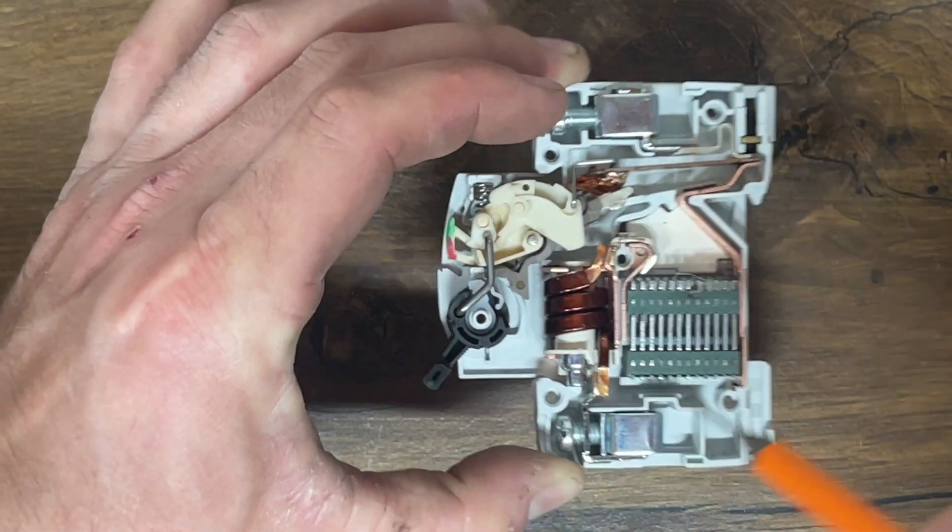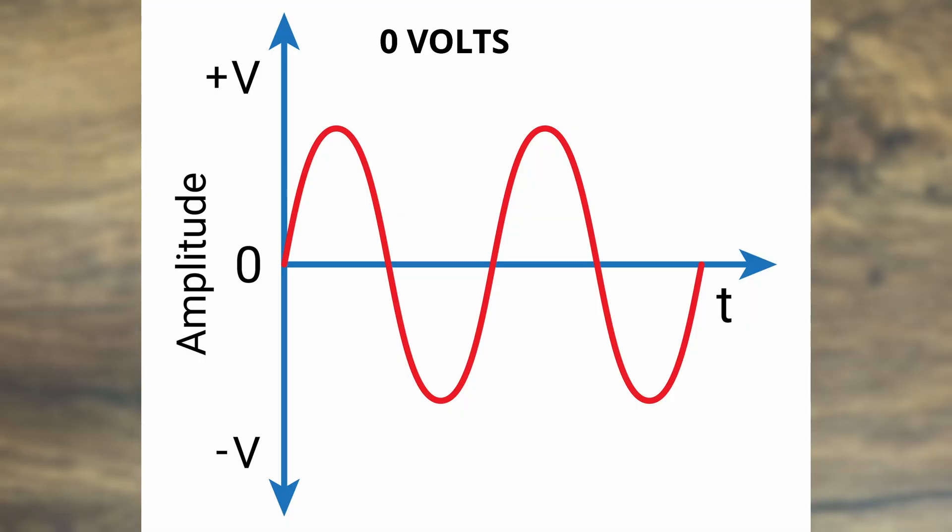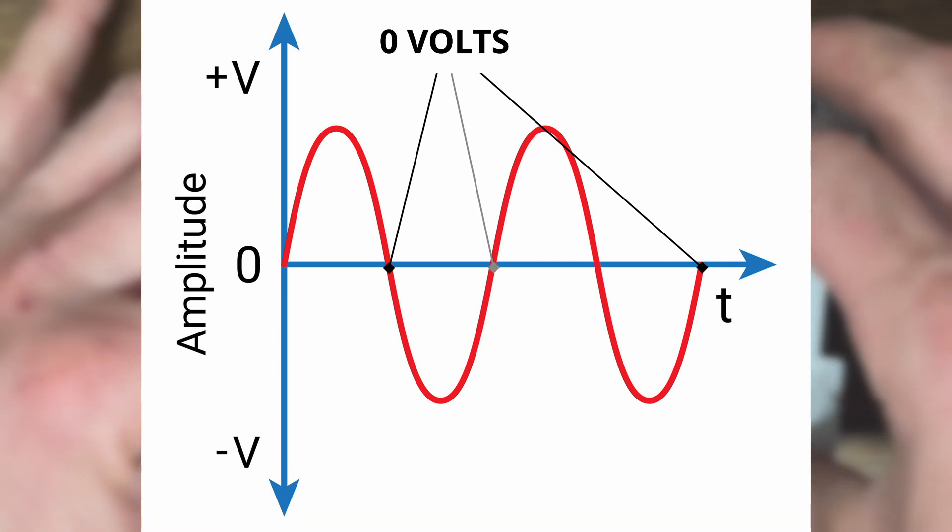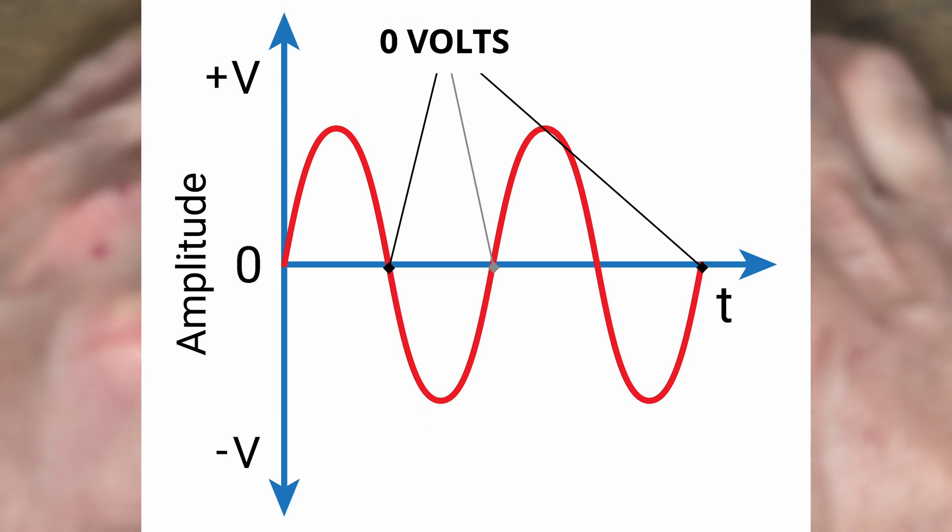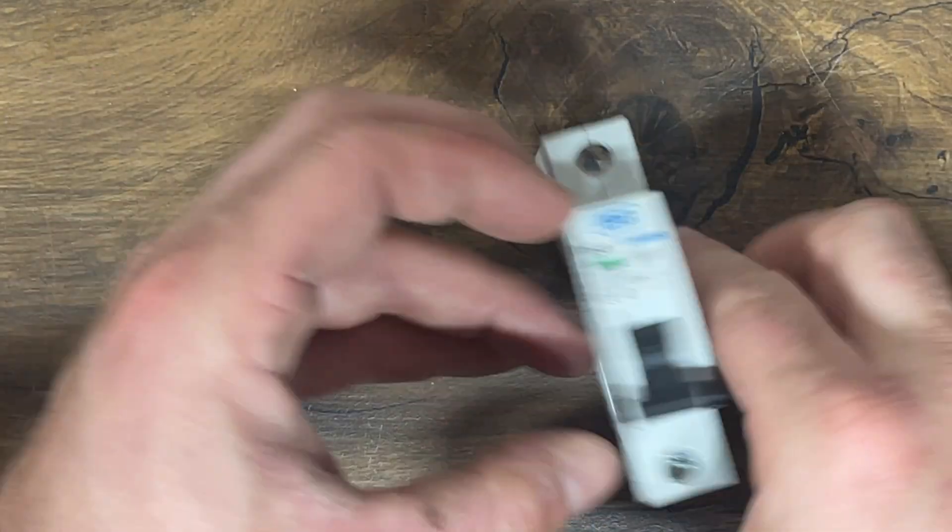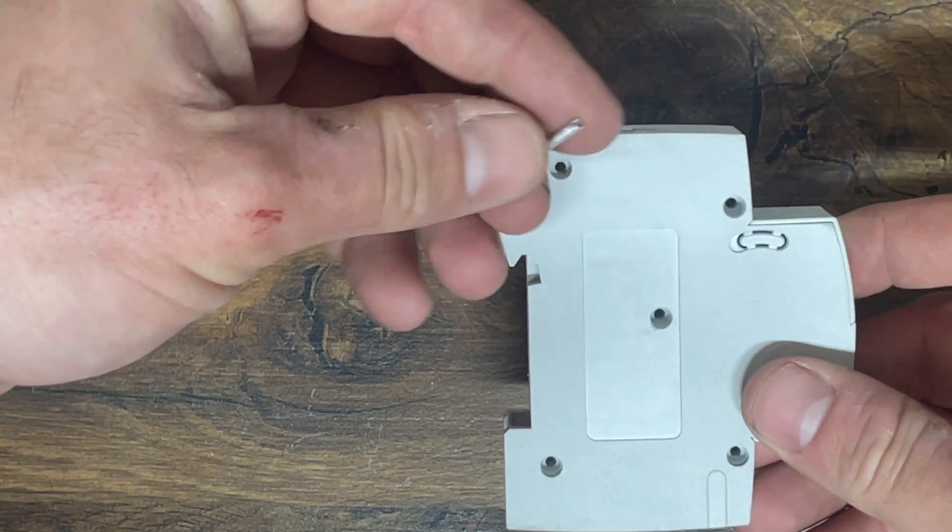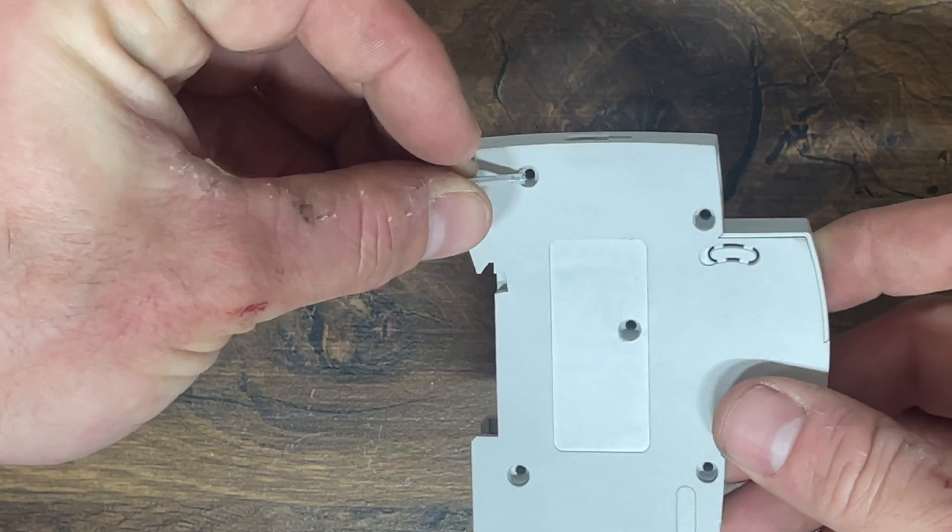DC MCBs are set up a little bit different because that arc doesn't break halfway through the cycle. So there we have the basics of our MCB. How about we jump to a cutaway version where we can see this MCB working in practice.